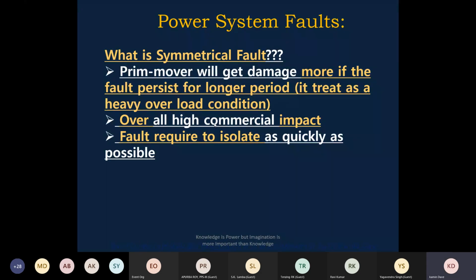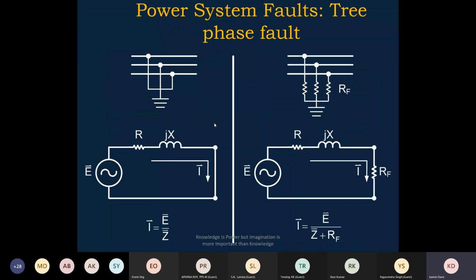So in that case, it has to be isolated as quickly as possible, as in 70-80 milliseconds. Okay, so if you look at it, a three-phase fault. This is on the left side. You see the three-phase fault, so I equals E by Z in that case, without fault resistance. Three-phase fault without fault resistance. And on the right side, you look at it here, fault resistance is introduced, RF. So I equals E divided by Z plus RF.